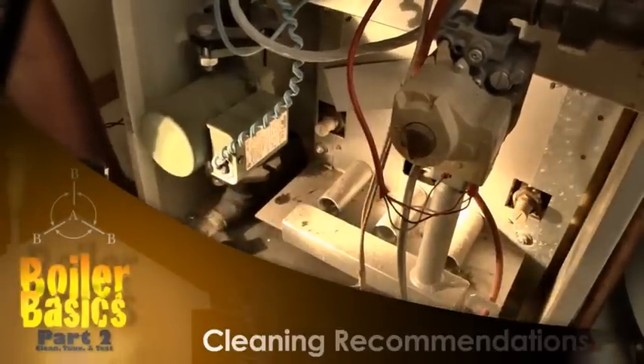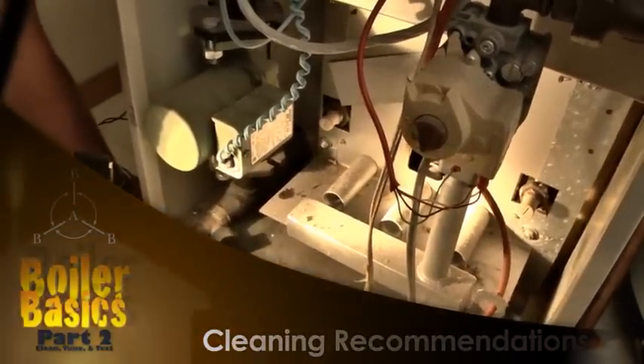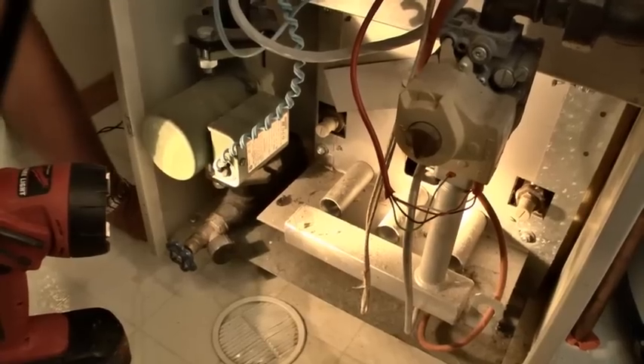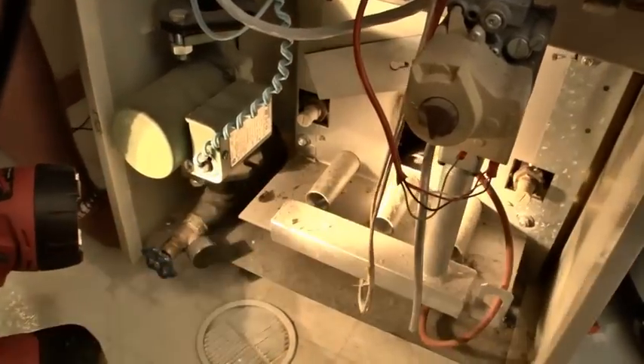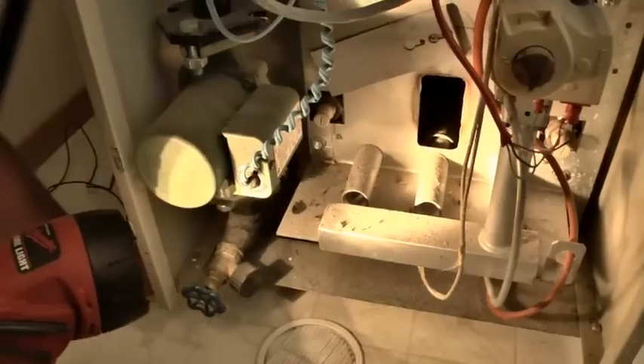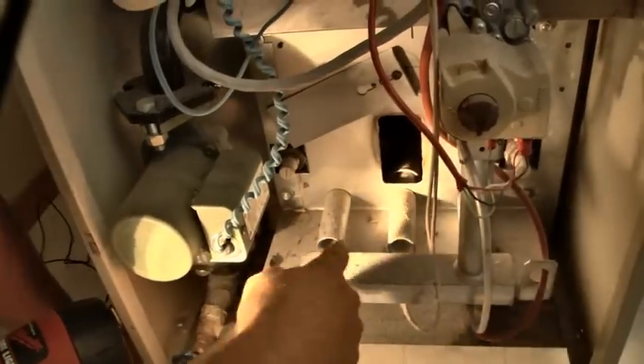Okay, one of the things we can do on a clean test and tune for a boiler is we can pull the burners and clean the burners, and cleaning up this area. This combustion air comes in here.